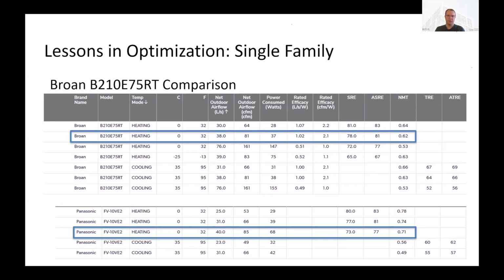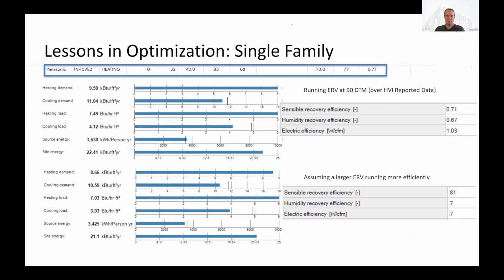And I don't want to say the Panasonics are bad or anything, right? If you were running this at 50 CFM and that was your target, then you're up at 83% for that sensible recovery efficiency, which would do the same thing here. It would look great, right? It's just this project needed 90 CFM, which is pushing the Panasonic further than it should be pushed.